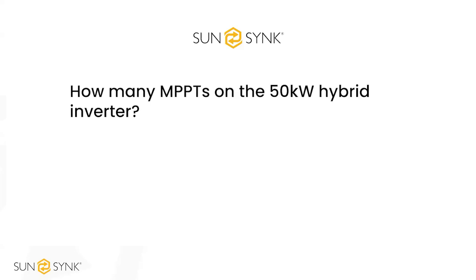For the 50 kilowatt hybrid inverter, how many MPPTs? On the 50 kilowatt, we've got 4 MPPTs with 2 strings into each. So we've got a total of 8 strings over 4 MPPTs.